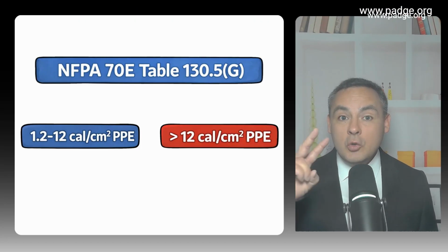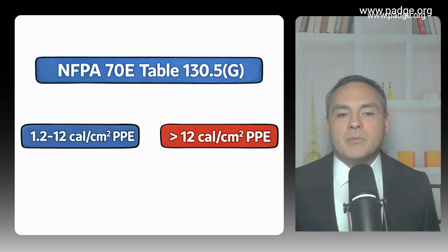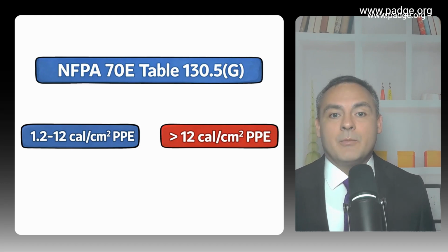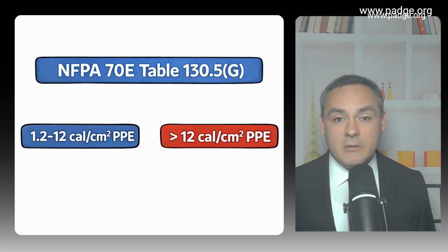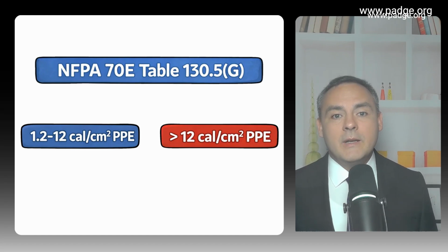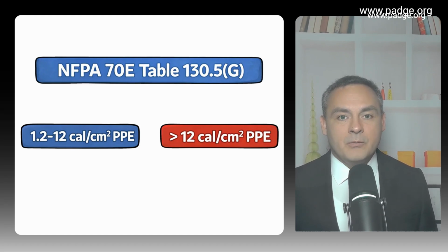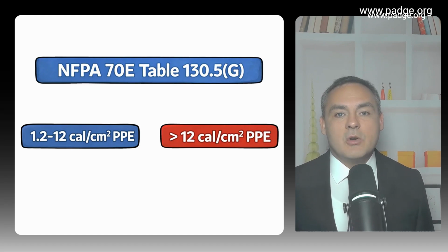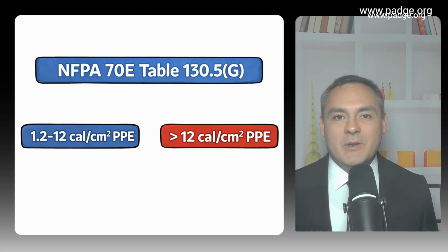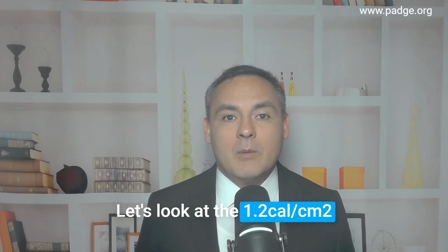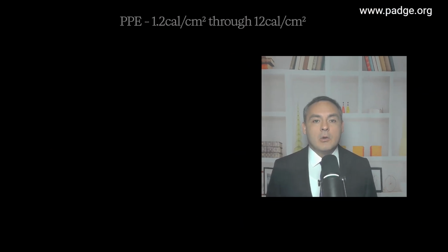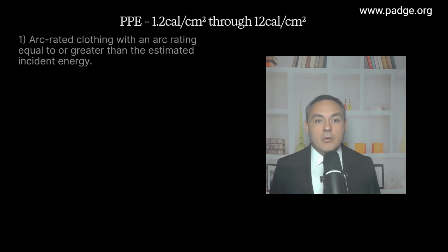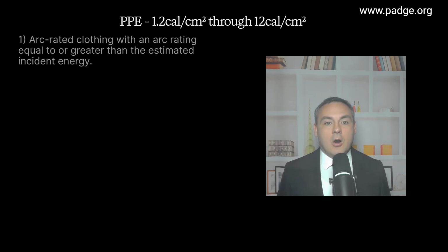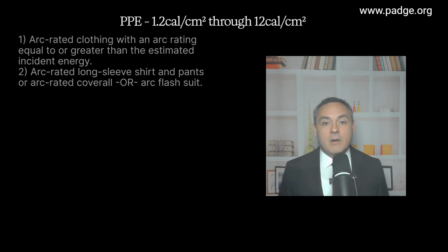They give two categories for arc-rated clothing in Table 130.5G. The first is 1.2 calories per centimeter squared up to and including 12 calories per centimeter squared. The second is incident energy exposures greater than 12 calories per centimeter squared. Let's look at the 1.2 through 12 category first. You're required to wear arc-rated clothing with an arc rating equal to or greater than the estimated incident energy: arc-rated long-sleeve shirt and pants or arc-rated coverall or arc flash suit.